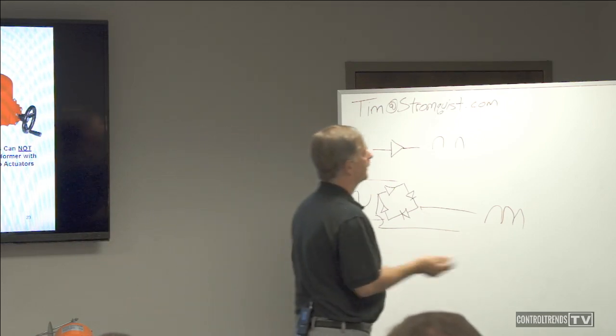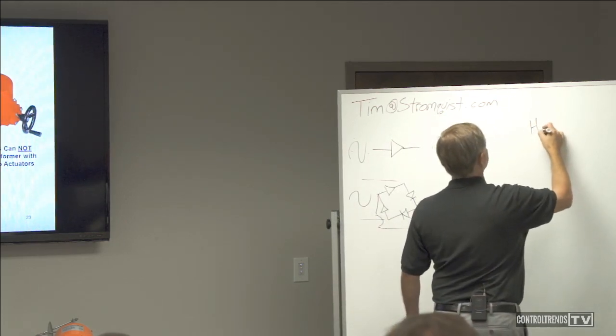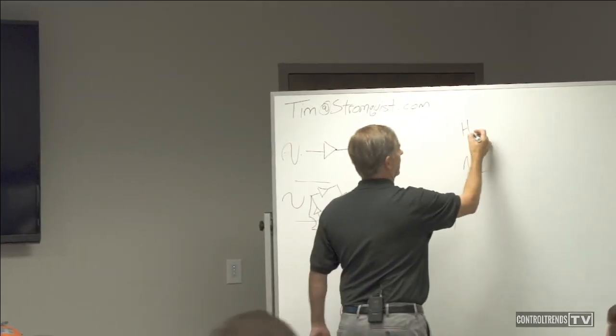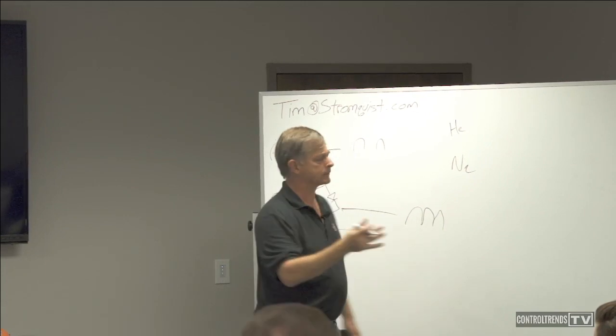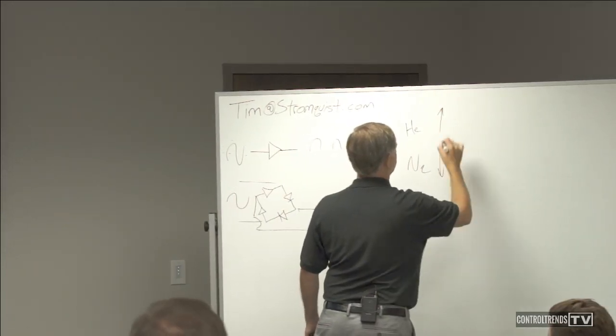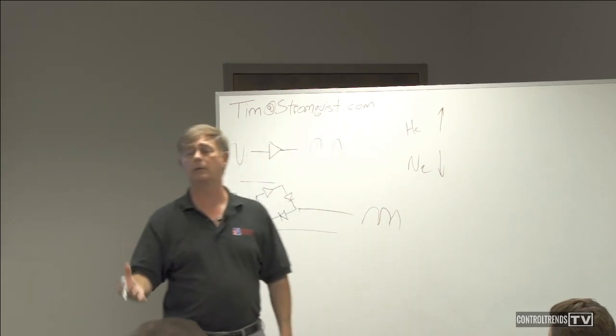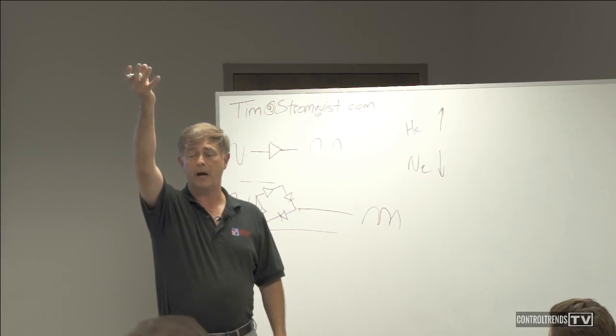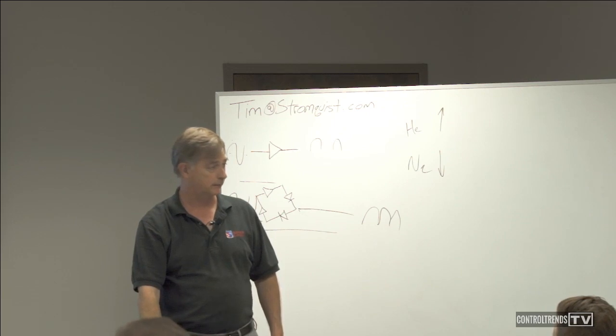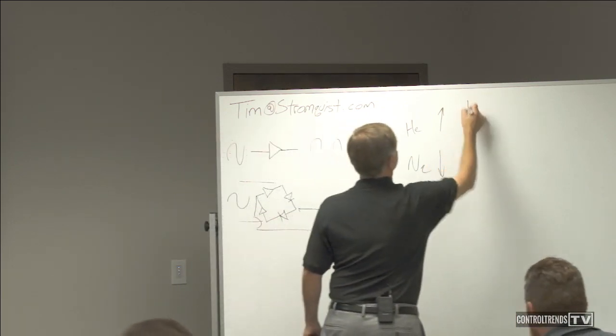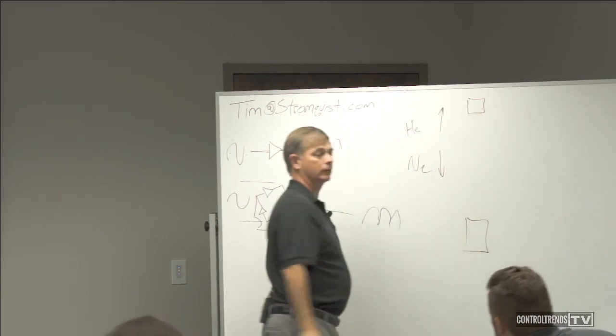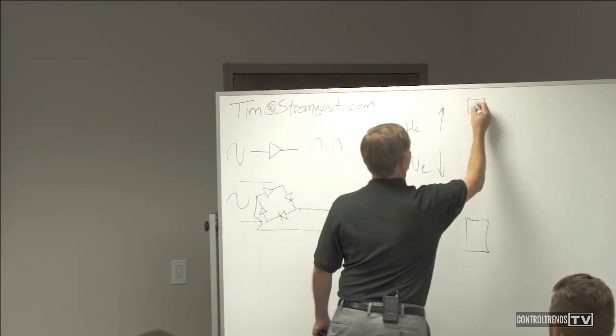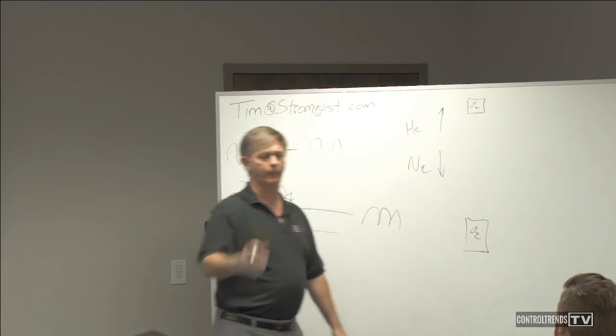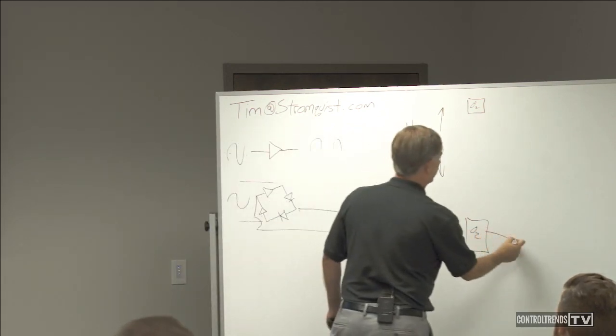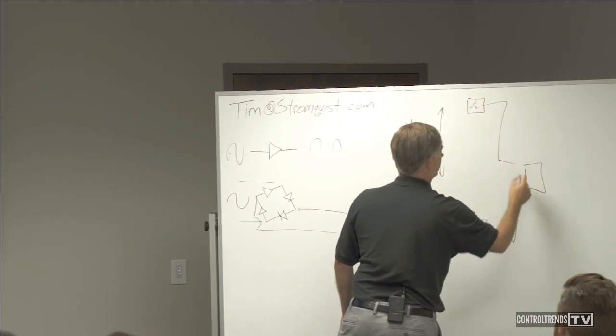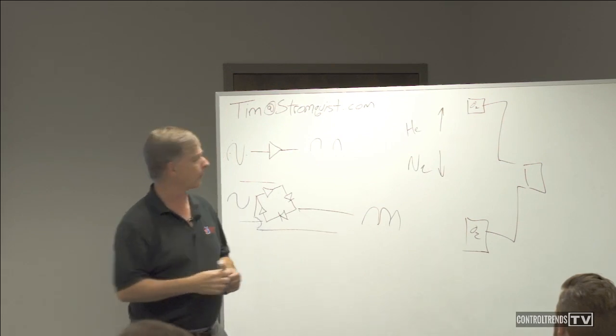All right, so we're looking at helium and nitrogen. They've got different weights. Helium is a lighter gas. Nitrogen is a heavier gas. So in this room, if one leaks, our problem would be high. If the other leaks, our problem would be low. Does that make sense? So what did we have to do? Well, we put a sensor high and we put a sensor low. We actually went with oxygen sensors, oxygen deprivation sensors. These sensors we tied into a little box that mixed the signals and sent out the lower of the two.